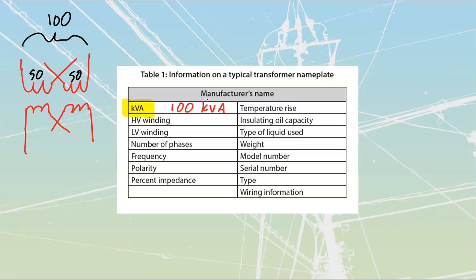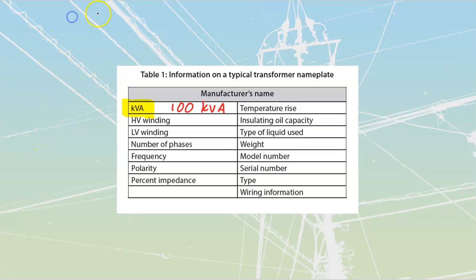High voltage winding. High voltage winding is going to be identified by its size and shape, but more importantly, high voltage is going to be identified by the letter H over here. Anytime that we see an H on something, that is going to be high voltage. If it's 2 windings, it's going to have only 1 to 2. If it's 4 windings, it is going to have 1, 2, 3, and 4. It's just going to be H with a subscript, or in a lot of cases when it's printed on the transformer, they just call it H1. They don't bother with subscripting.